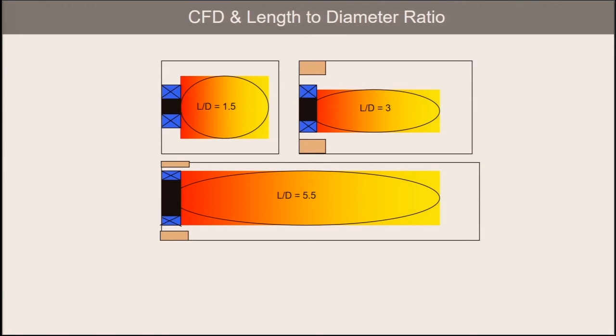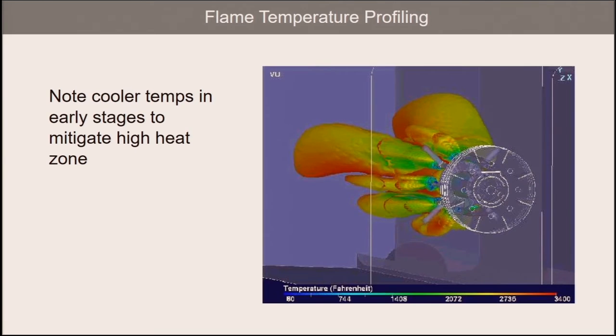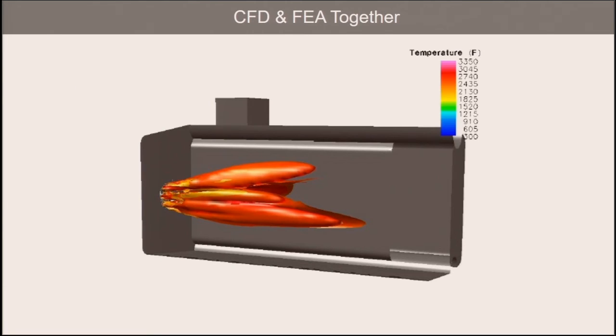Computational fluid dynamic programs go beyond calculating length and diameter ratios — these programs will also foretell, based on mass flows of fuel and air, what the velocities and temperatures will be as the flame progresses down the furnace. To mitigate NOx production, we need to limit temperatures without quenching the flame while also limiting the amount of time the combustion process lasts within the furnace. Combined with CFD is finite element analysis (FEA), a sophisticated mathematical analysis tool that proves what was determined with the computational fluid dynamic interplay is also legitimate.